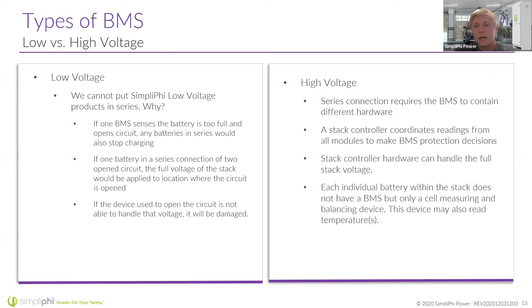However, with a high voltage product, you often have a stack controller. The stack controller is the only device that would ever open the circuit. Each individual battery does not have a BMS that can open the circuit fully within each battery. It's only going to have a cell measuring device, balancing device, maybe monitoring within each cell pack and battery pack, but it's not going to have a full BMS until you get to the very top of the stack. That stack controller is the BMS, and it can handle the full voltage that you're giving to it. That is how you get around a BMS in high voltage scenarios.